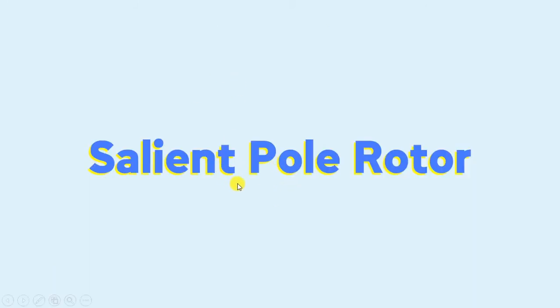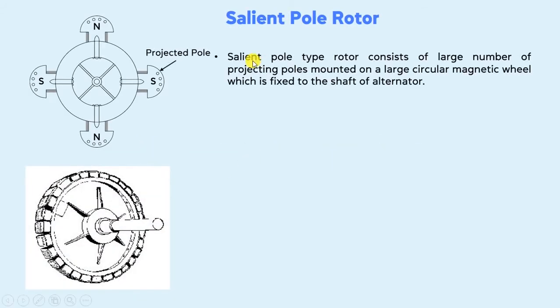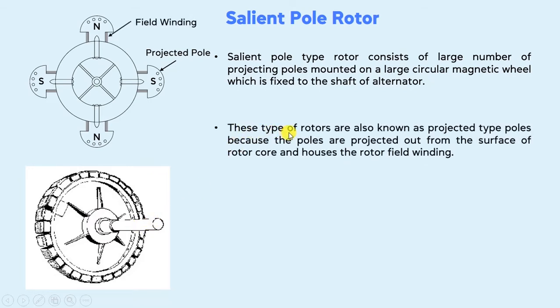First of all, we will discuss the salient pole rotor. Salient pole type rotor consists of a large number of projecting poles mounted on a circular magnetic yoke which is fixed to the shaft of the alternator. Here you can see these are the projected poles, this is the circular magnetic yoke, and this is the cross-sectional view of the salient pole rotor. These types of rotors are also known as projected type rotors, because the poles are projected out from the surface of the rotor core and house the rotor field winding.